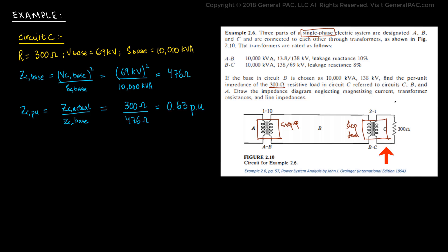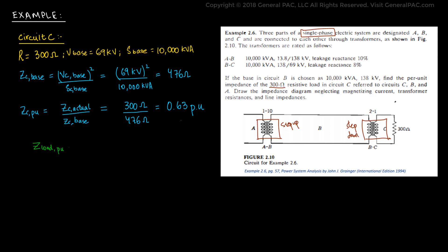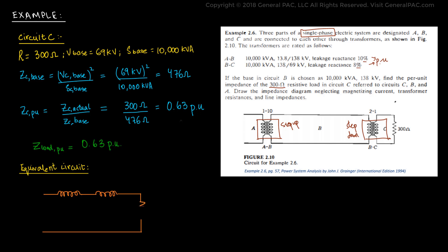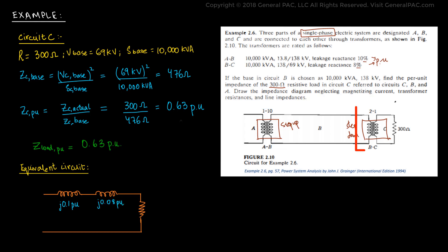Based on Part 2c of this series, we already know the per unit impedance for both transformers and the load. The load per unit impedance was calculated as 0.63 per unit. Since the transformer leakage reactances were given as percentages with the same power base, they already correspond to per unit values. So the equivalent circuit has J0.1 per unit for the first transformer, J0.08 per unit for the second transformer, and 0.63 per unit for the resistive load. We already have the equivalent circuit for the entire problem.